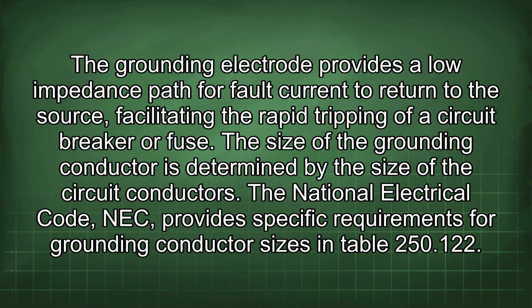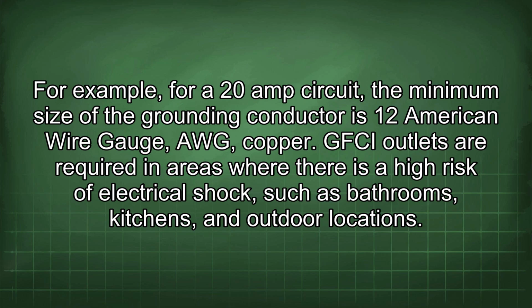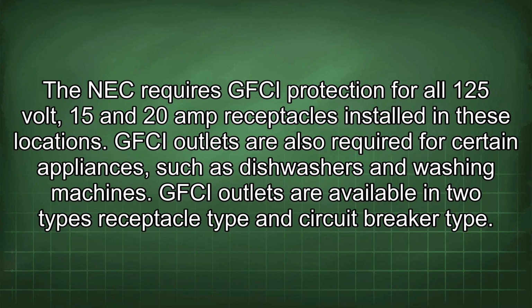The size of the grounding conductor is determined by the size of the circuit conductors. The National Electrical Code, NEC, provides specific requirements for grounding conductor sizes in Table 250.122. For example, for a 20 amp circuit, the minimum size of the grounding conductor is 12 American wire gauge, AWG, copper. GFCI outlets are required in areas where there is a high risk of electrical shock, such as bathrooms, kitchens, and outdoor locations. The NEC requires GFCI protection for all 125-volt, 15 and 20 amp receptacles installed in these locations. GFCI outlets are also required for certain appliances, such as dishwashers and washing machines.